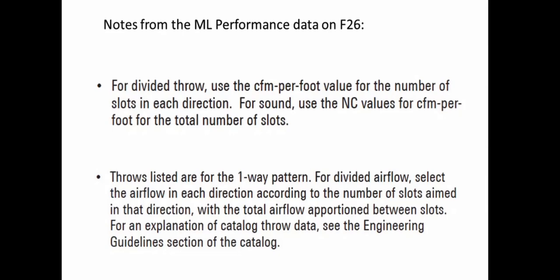The ML throw is calculated in the same manner, and the notes at the end of the performance data section are a reminder that throw is proportional. We hope this podcast has been enlightening, and just remember, pressure and noise are based on total airflow, throw is proportional to the number of slots.